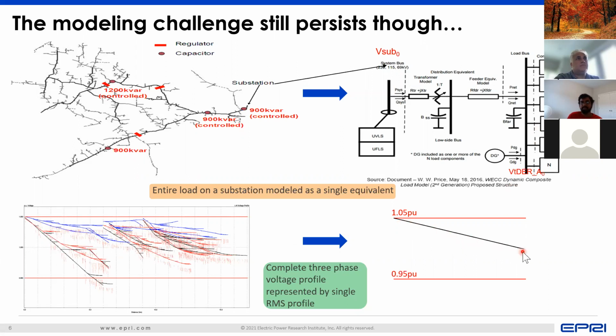And we have to essentially ensure that this entire voltage profile that you see here is represented by a single phase RMS voltage profile, and it's still able to provide all of the characteristics that elements inside the feeder, which would use each of these individual voltage levels, have to behave. We have to ensure that the characteristic of this feeder is represented by using this aggregated model. So we know that we have to use aggregated models. We understand that the sufficiency criteria has to be met.